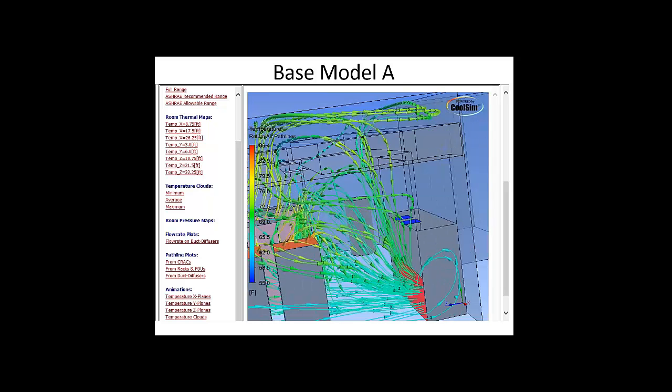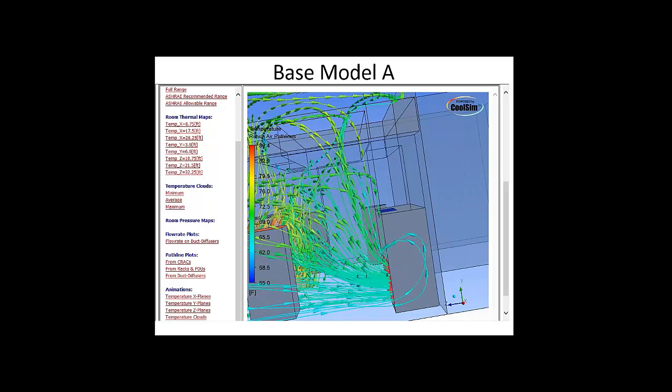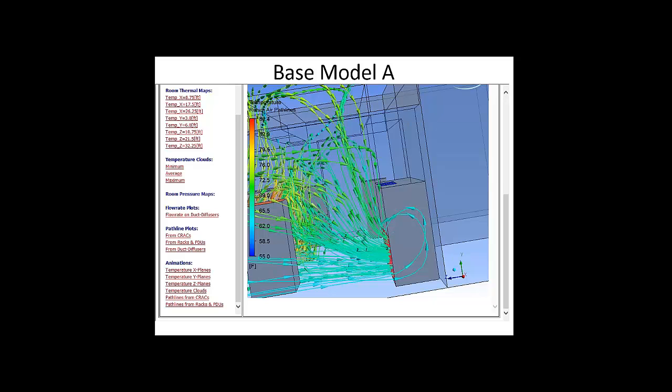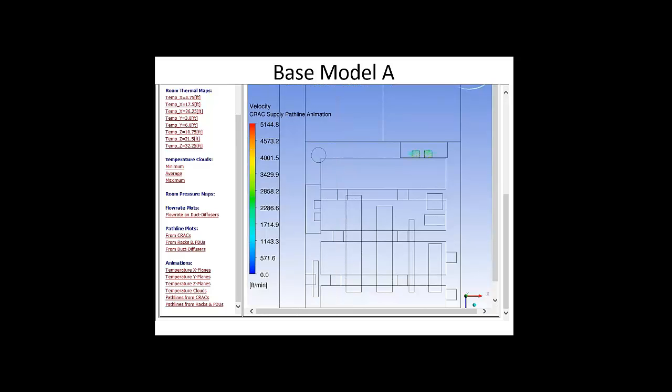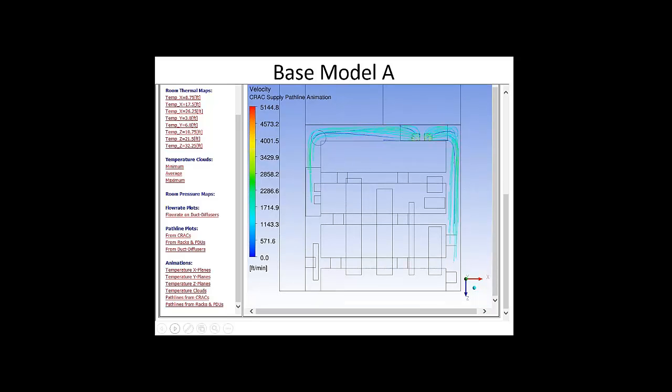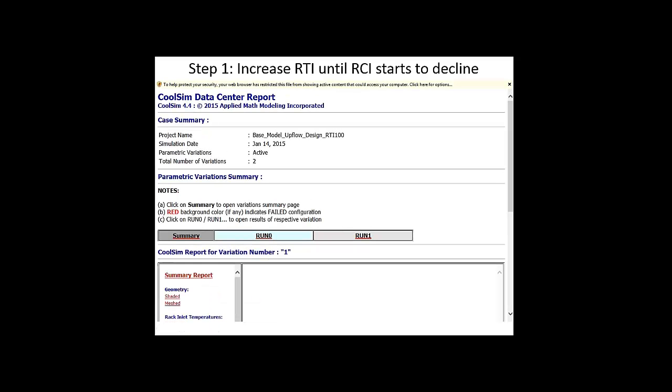So this is a fundamental problem. I see this a lot in these kinds of data centers, and that CRAC unit may be rated for a certain capacity, but it's certainly going to run well below that rated capacity. There's also a series of animations here that show the sequence, but in the interest of time, we'll just move ahead.